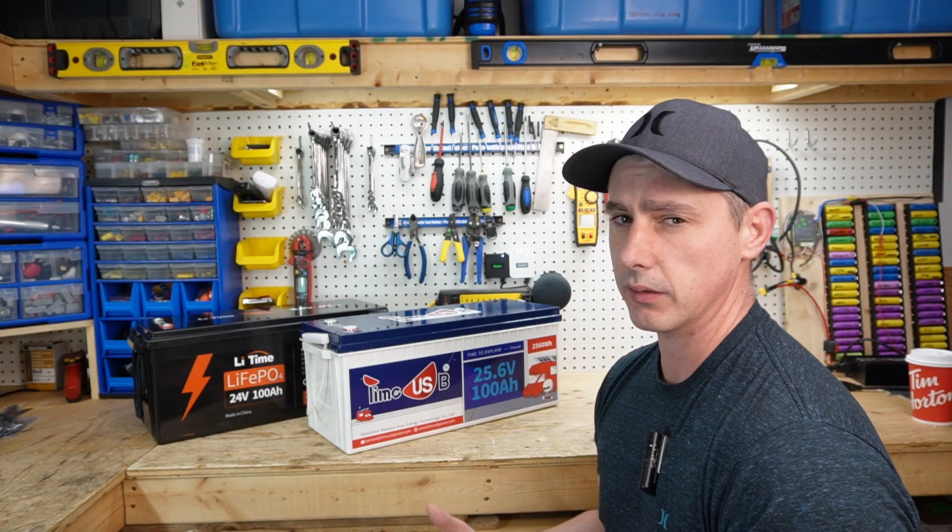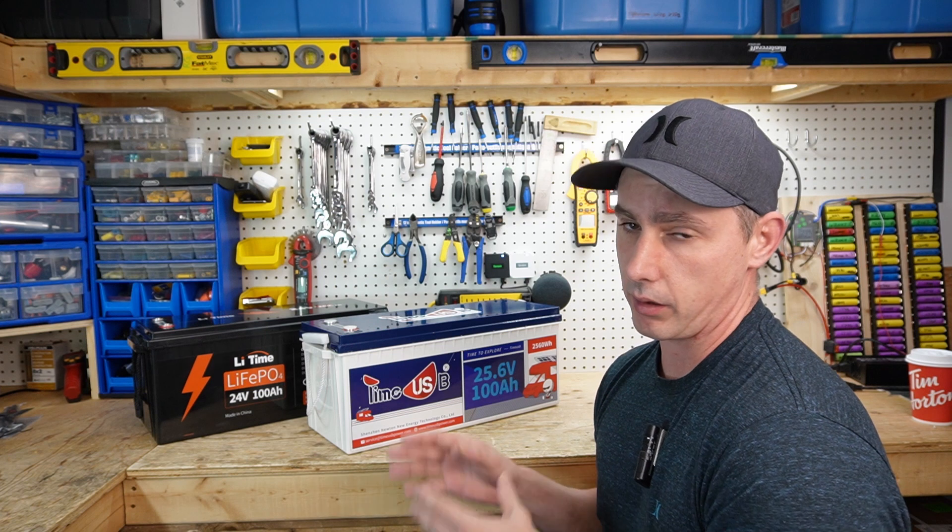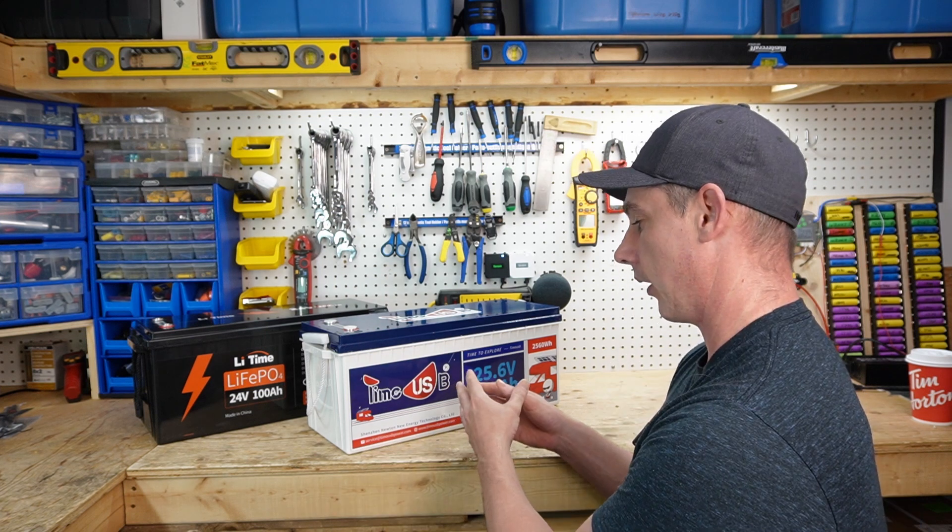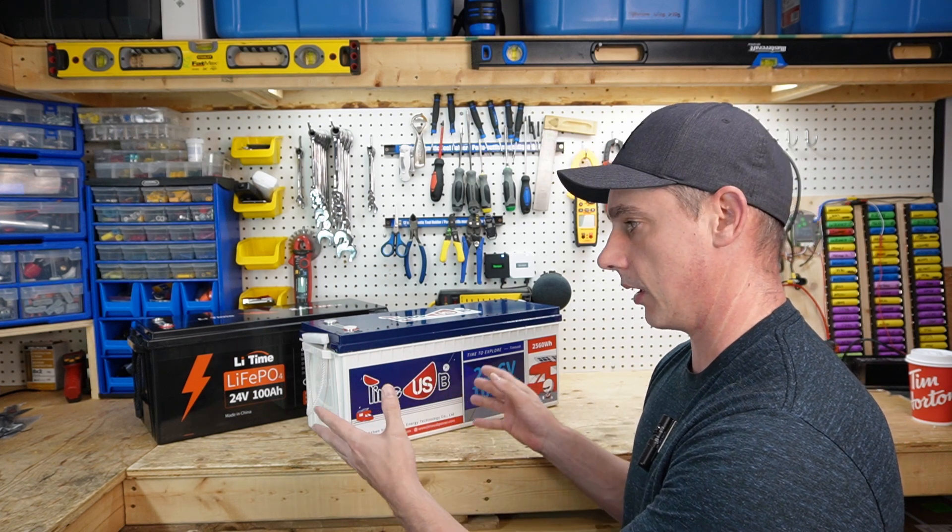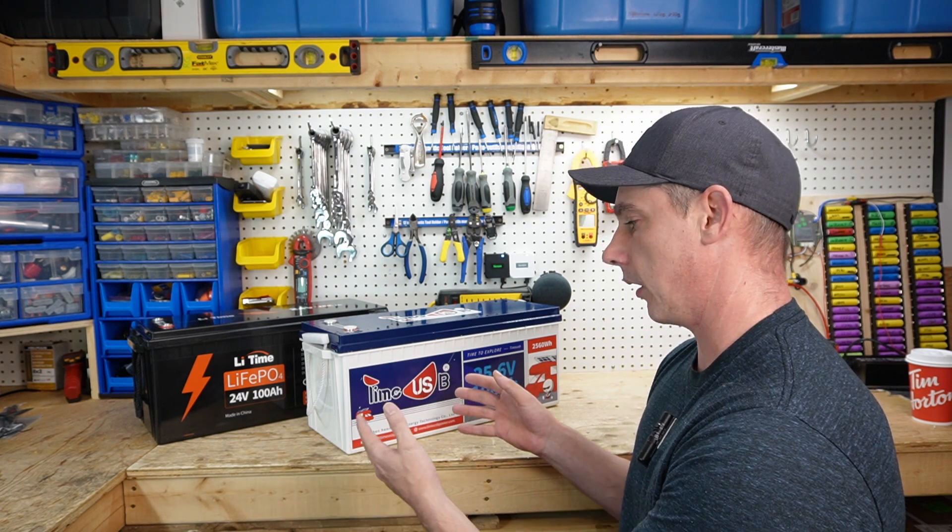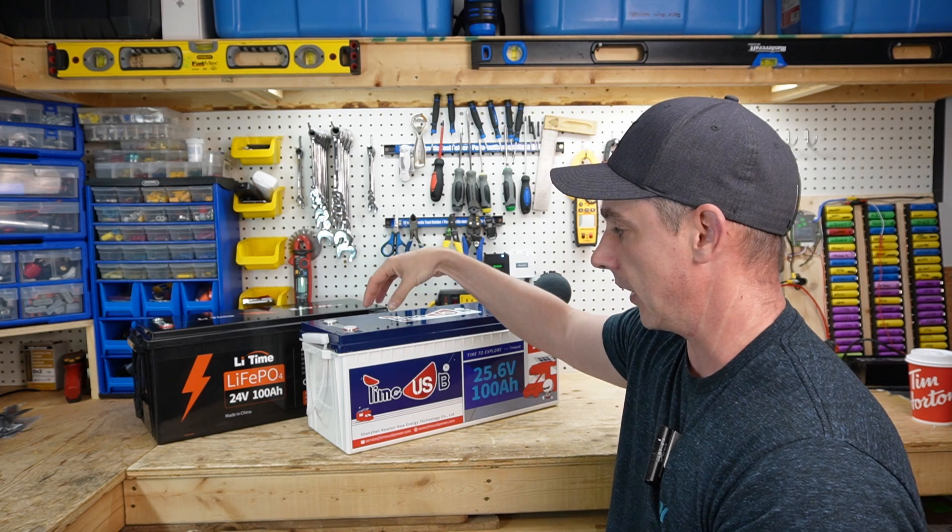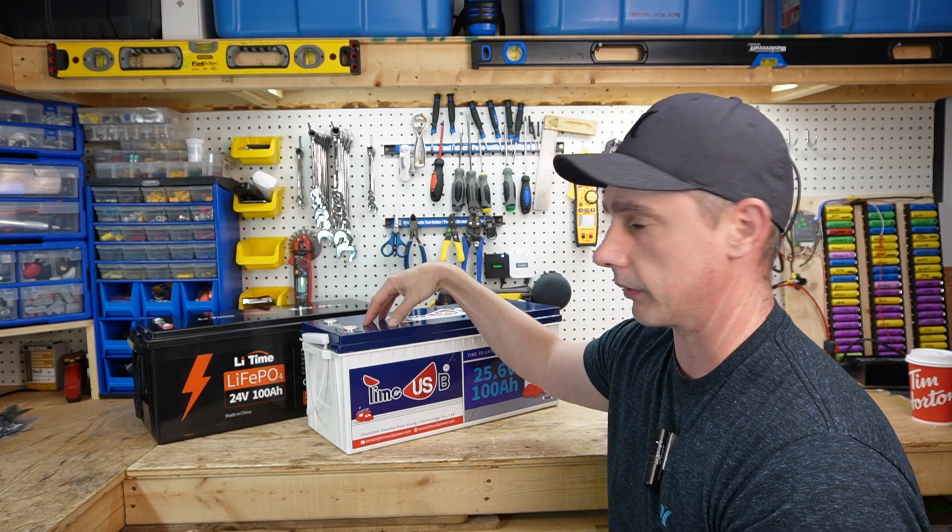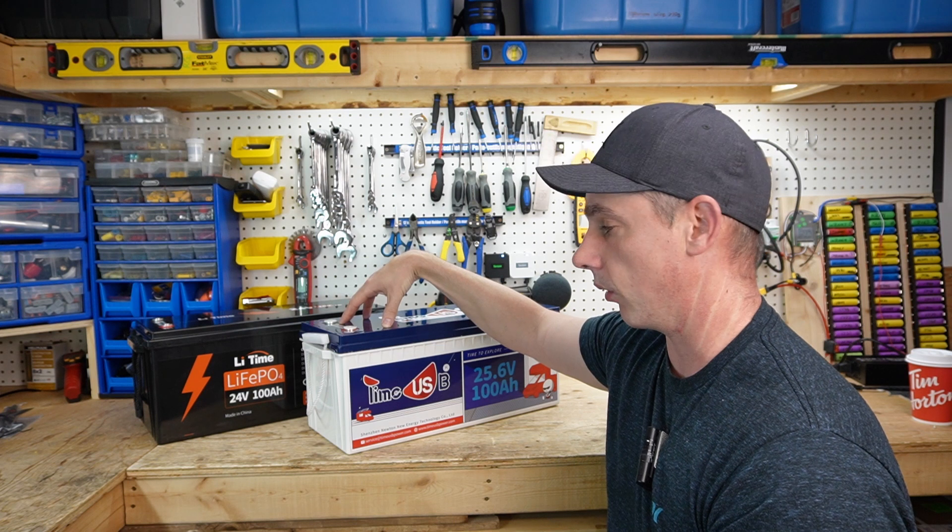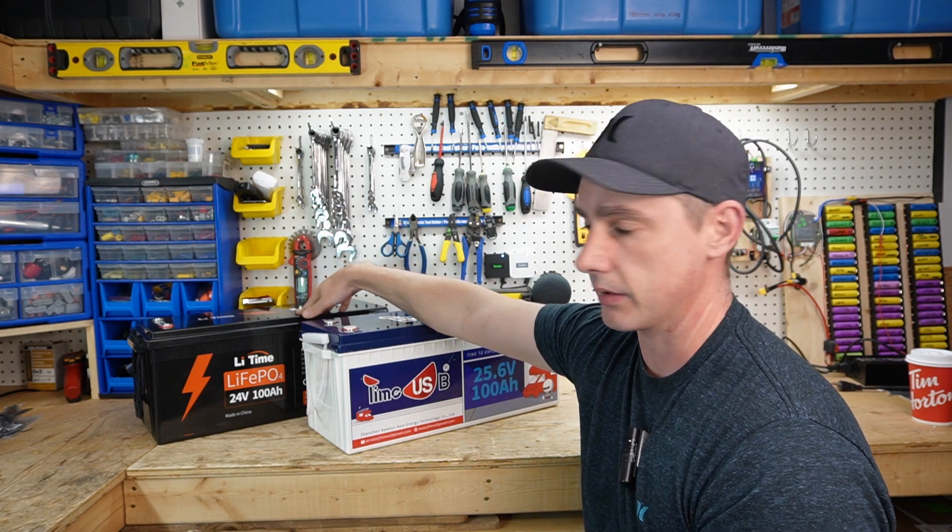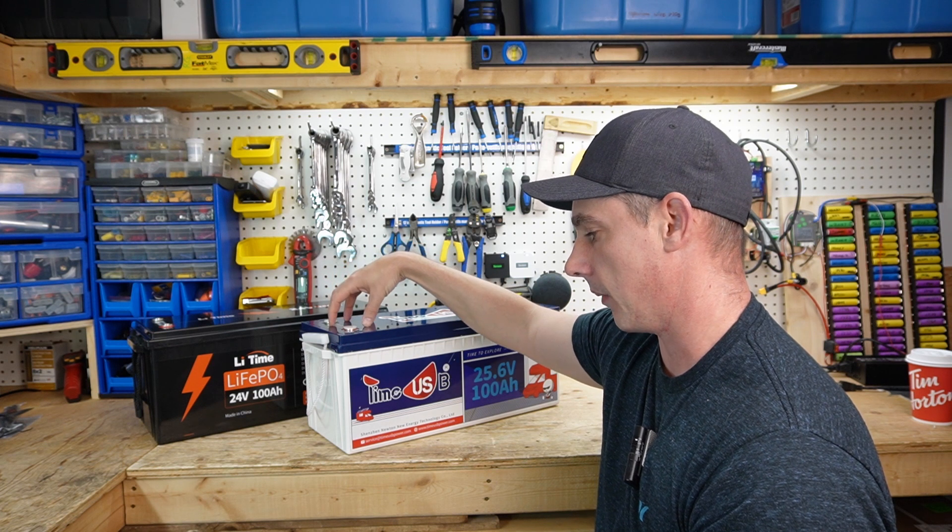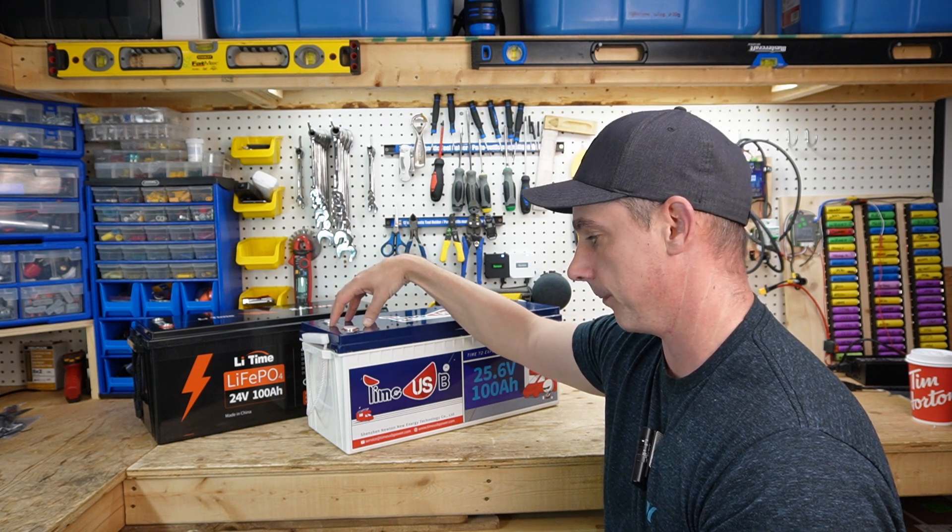Now it is ideal to buy your batteries at the same time and of the same brand. You have a higher possibility of all the cells being matched and of the same quality and manufacturing style, because what can happen when you connect them in series, if this battery pack has more internal resistance than this battery pack, then this one is going to hit low voltage disconnect and this one is just going to sit idle until you get some charge back into the battery and this comes back up to the proper voltage.